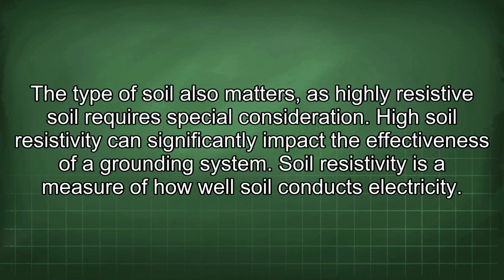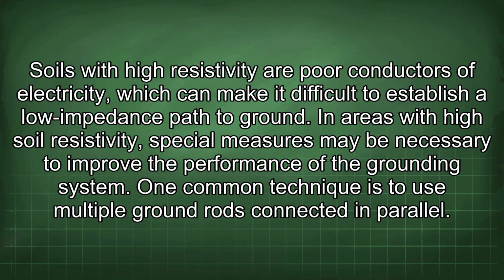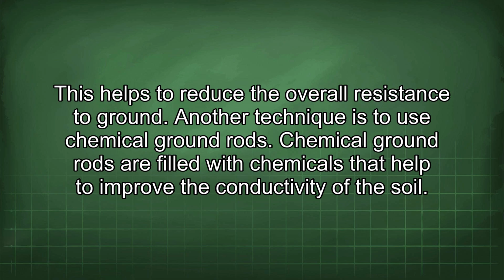The type of soil also matters, as highly resistive soil requires special consideration. High soil resistivity can significantly impact the effectiveness of a grounding system. Soil resistivity is a measure of how well soil conducts electricity. Soils with high resistivity are poor conductors of electricity, which can make it difficult to establish a low impedance path to ground. In areas with high soil resistivity, special measures may be necessary to improve the performance of the grounding system. One common technique is to use multiple ground rods connected in parallel. This helps to reduce the overall resistance to ground.